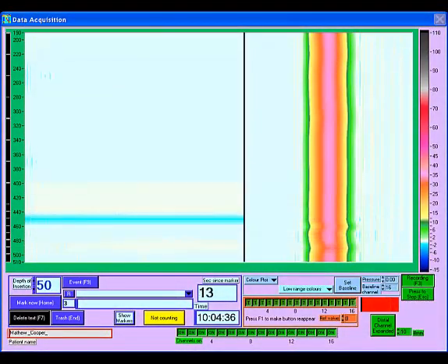In the colour plot graphs, you will see the background colour change to white, indicating that the pressures are now 0. And in the line plot graphs, you will see the current values at the right hand end change to 0. When the channels are perfusing and stable, the background should remain a constant colour, preferably white.